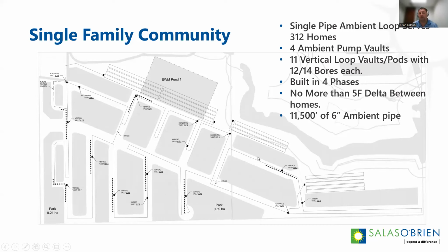So even though they are getting different temperatures, this allows us to downsize the single pipe and slow the water flow down, which lets us use smaller pumps that use less energy. So we're not over-pumping and creating parasitic losses in the system.